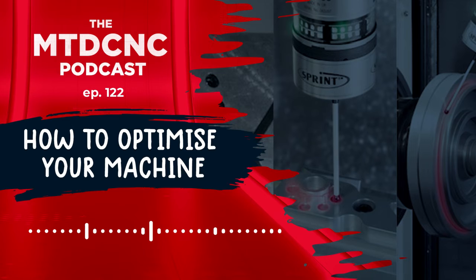So that's really important when you're talking about things like blades. If you've got a blade or a blade on a blisk that you need to measure, you won't be able to access the entire perimeter of a cross-section of that blade. You need to position the rotary axes in order to get access for the stylus to get in and scan those various different patches. So 5-axis technology does increase the capability of the Sprint system, certainly.